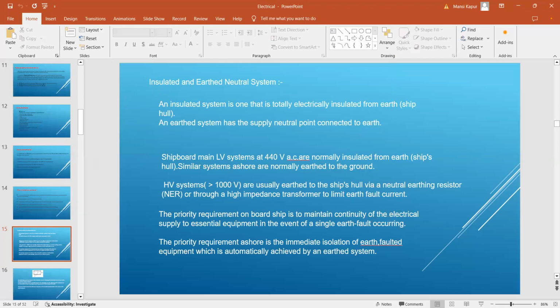Understood this much? Yes, sir. An earth system has the supply neutral point connected to the earth. So here the neutral point is connected to the earth, and in the first one the neutral point is insulated. Shipboard low voltage systems like 440 AC are normally insulated from the earth. So when you are sailing on the ship, like your oil tanker, it must be low voltage, right? You are not generating more than 1000 volts, right? Yes, sir. So you are sailing on a low voltage ship, and on your ship the system will be the insulated earth system.